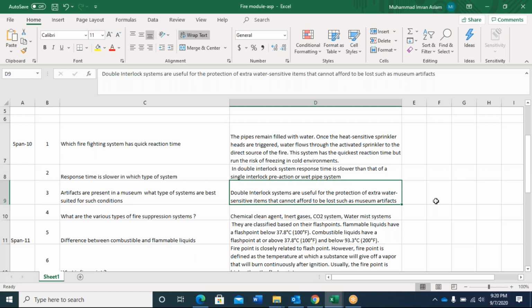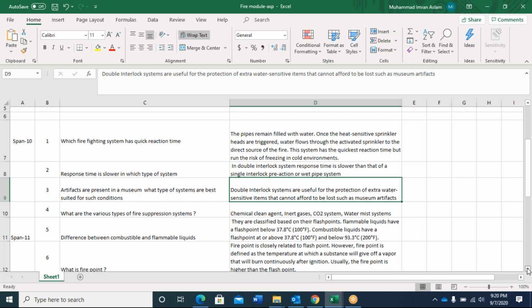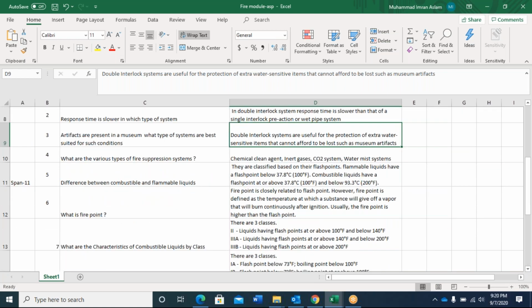There is a sensor, one detection device available which detects if there is a fire in the workplace. Or the second condition is there is a fuse bulb available, which should melt away. If only the fuse bulb melts away, then the air is released and the water sprays on the work area. Then we call it a single interlock system.